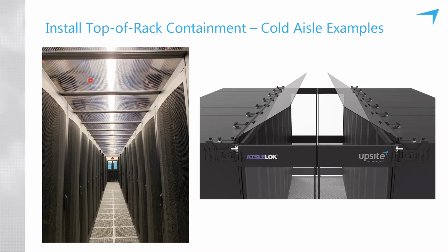So you buy these things at different widths to span the aisle. This is a 48-inch aisle. These things either rest on or mount on the cabinets across the aisle from one another. So that's an example of a capped or fully enclosed roof for cold aisle containment. Thank you, Rob.